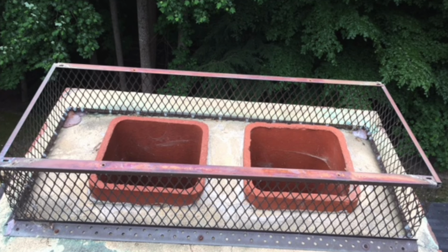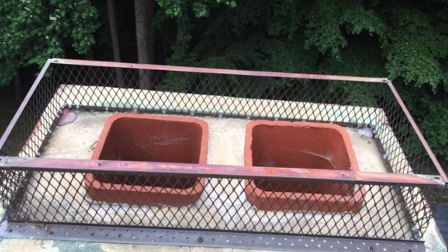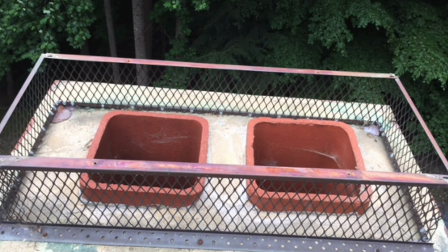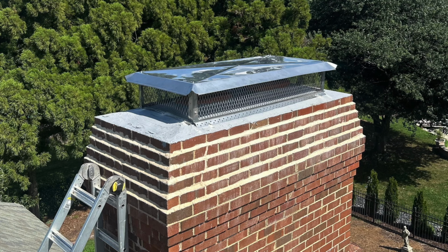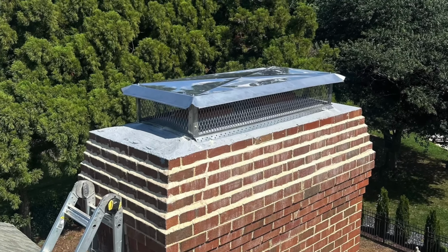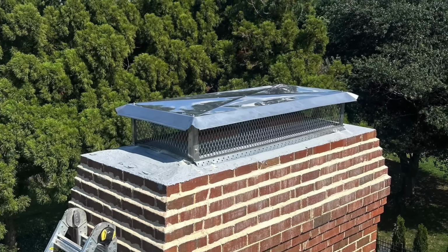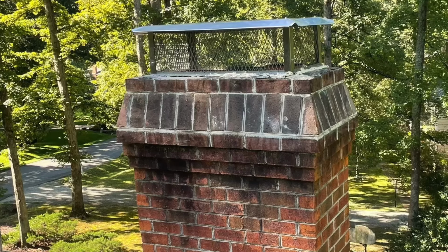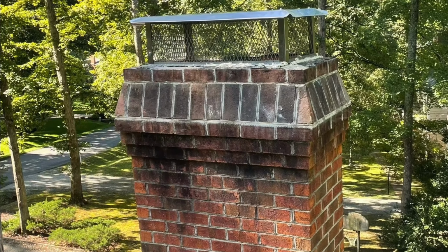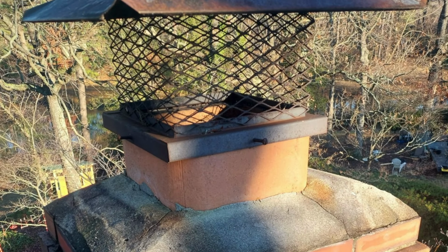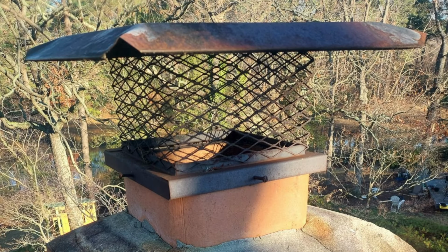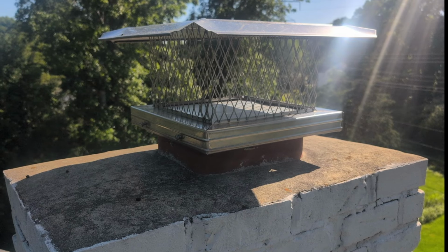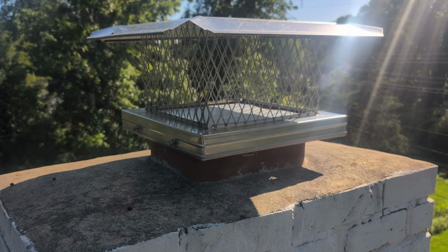For example, if a multi-flue cap is covering 2 flues that each measure 13 by 13 inches, the lesser dimension is 13 inches, meaning the underside of the chimney cap must be positioned at least 13 inches above the top of the highest flue. This requirement ensures that the cap provides adequate clearance to maintain proper draft while preventing turbulence, smoke spillage, or heat buildup that could damage the cap or the chimney structure. Collectively, these requirements ensure that chimney caps and spark arresters function safely, maintain proper draft, and comply with national standards for performance and fire protection.